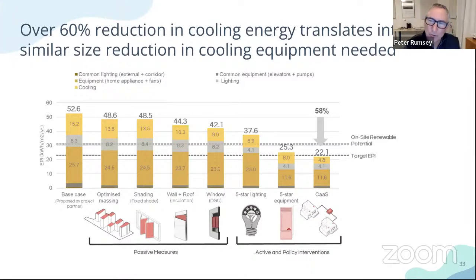The energy use did sort of follow the cooling system sizing. If you look, the cooling energy was 15 units on the base building, the typical building, and 4.8 units for this one, annual energy use. But the cooling system sizing was probably reduced by over 60%, maybe 70%. I don't know their final number, but it was somewhere in the 60% reduction in the peak cooling, the maximum cooling needed.